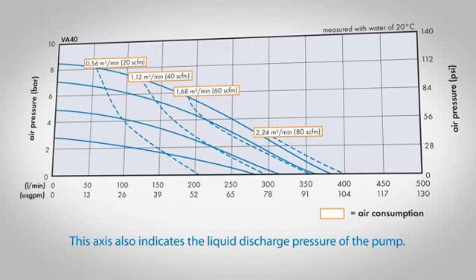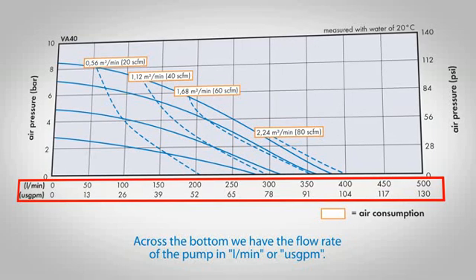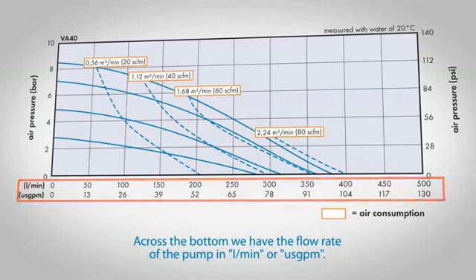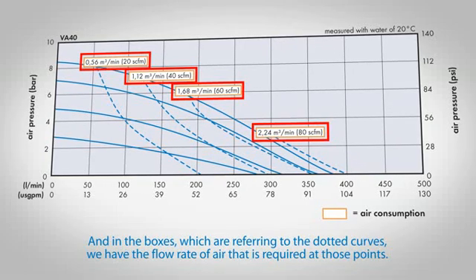This axis also indicates the liquid discharge pressure of the pump. Across the bottom we have the flow rate of the pump in liters per minute or US gallons per minute, and in the boxes which are referring to the dotted curves we have the flow rate of air that is required at those points.